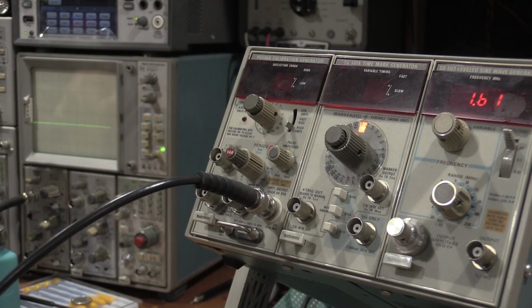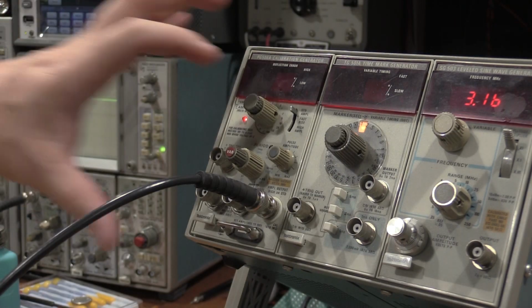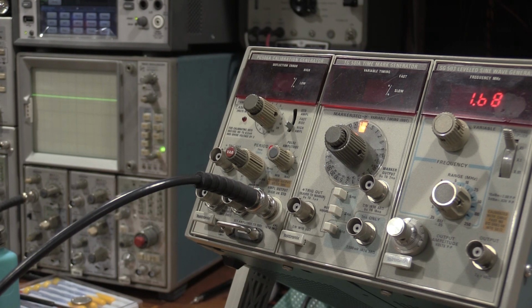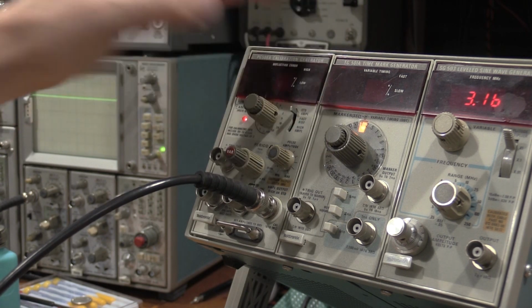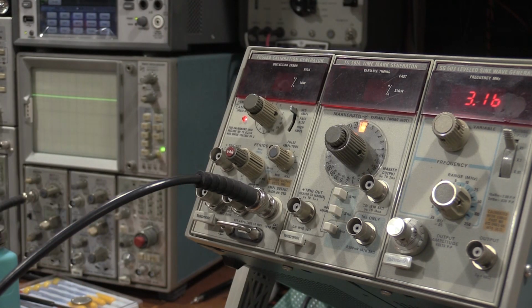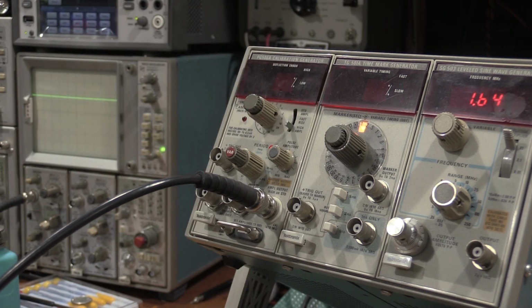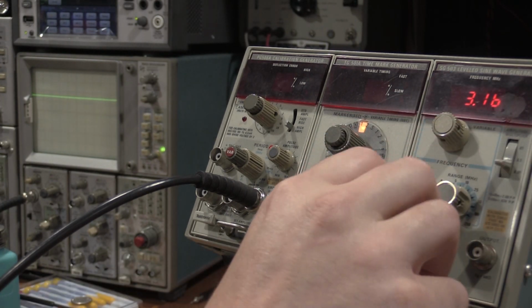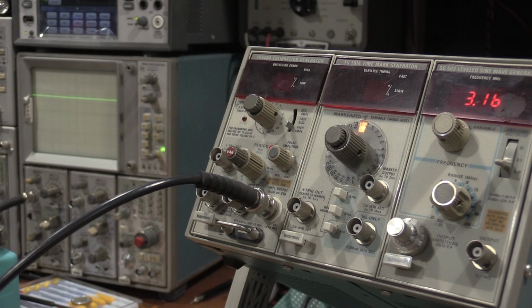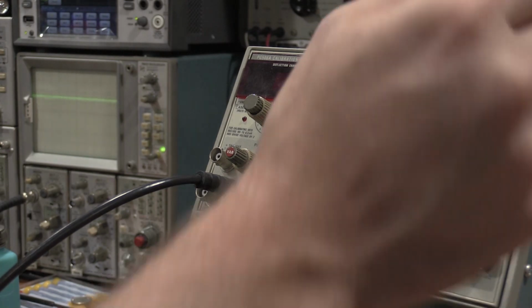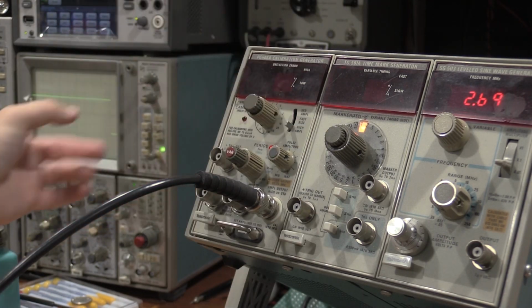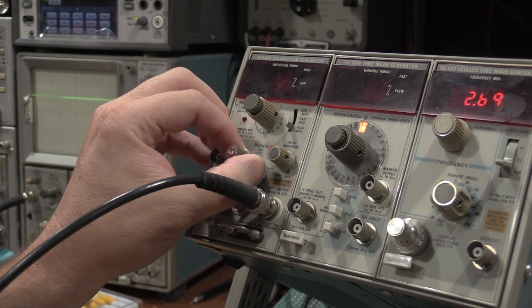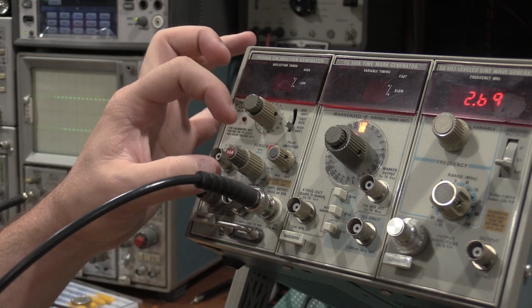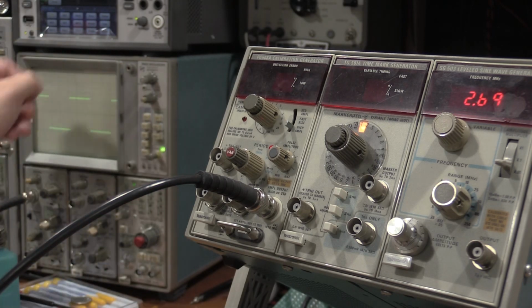Let's see if high amplitude's working. Okay, that's weird. These plugins should not talk to each other. I switched this to high amplitude with it set to minimum, and the frequency goes nuts on the SG503. So that's strange, to say the least. Okay, I can adjust amplitude. And I can adjust frequency. So that's working.